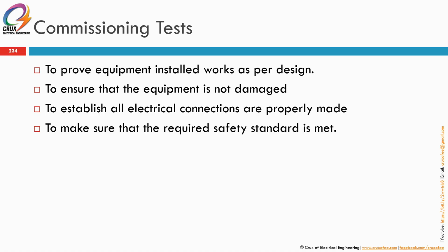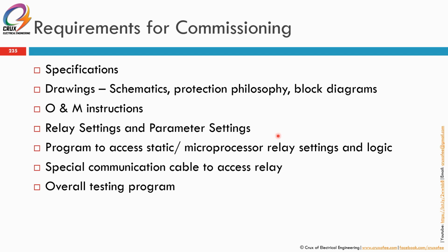So after you all have installed the protection system, switchgear, motor, transformer, and all the electrical equipment, this is the final test for your equipment, which is your SAT or your commissioning test. Commissioning is to prove whether the equipment installed works as per design, to ensure that the equipment is not damaged, to establish that all electrical equipment connections are properly made, and to make sure that the required safety standard is met. So this is on the commissioning test.